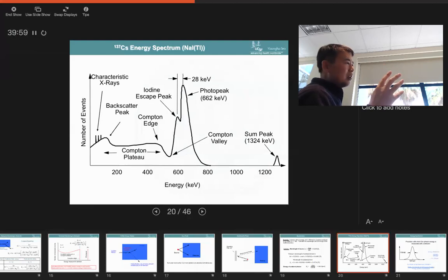Why X-ray emission? The same thing. Photons interact by the photoelectric effect, and then there could be some X-rays by transitioning from the L shell to the K shell. These X-rays come from all these different materials around it, including the detector material. There are some portion of X-rays coming out because of all these issues. So there are multiple characteristic X-ray peaks depending on which material was the source. You can actually see the different materials by looking at characteristic X-rays measured in the energy spectrum.